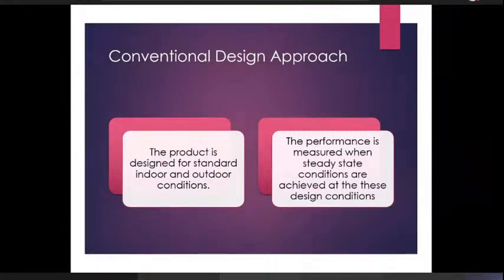Now, the important thing is that when you look at a variable speed system, we can't look at fixed point performance. Then we need to make assumptions on what percentage of the time during its life an air conditioner will work at part load conditions. So what weight do we assign to the energy efficiency ratio at part load, and what weight do we assign to the energy efficiency ratio at full load?